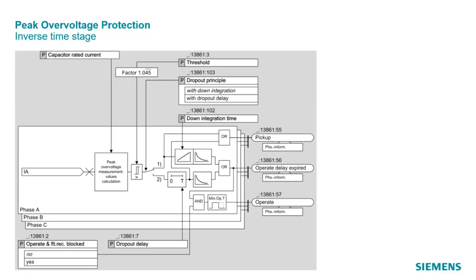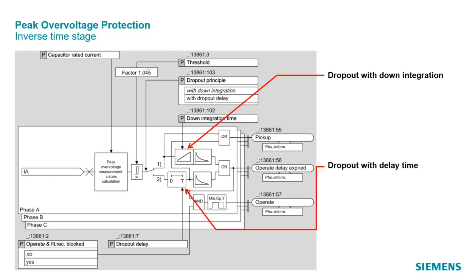The function offers two different delayed drop-off methods. The first is called drop-out with down integration: the pickup resets immediately, but the operate delay timer is counted down from the last reached value to zero linearly. With a new pickup, the time starts from the last time value reached during the countdown. As a difference, the drop-out with delay time keeps the pickup for a settable time where the operate delay timer remains frozen. If the pickup returns, the operate delay timer starts from the frozen value. These methods ensure that returning short voltage peaks will also lead to a tripping command, even if the duration of each single voltage peak is too short for tripping according to the characteristic.